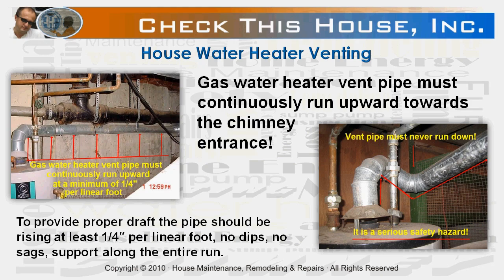Gas water heater vent pipe must continuously run upward towards the chimney entrance. To provide proper draft, it should be rising at least a quarter of an inch per linear foot. No dips, no sags — proper support is required along its entire run. Some installations might be a significant challenge or even become impossible due to water heater height, location, and chimney flue connection level. In such cases, consider using an induced draft motor equipped water heater.